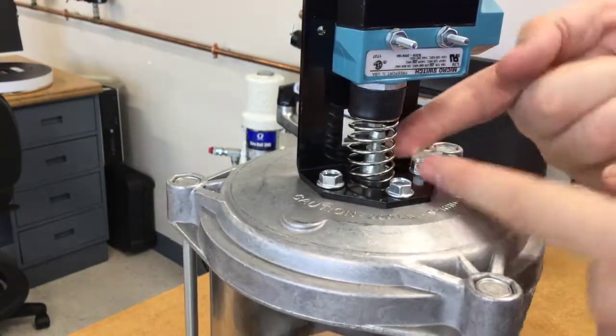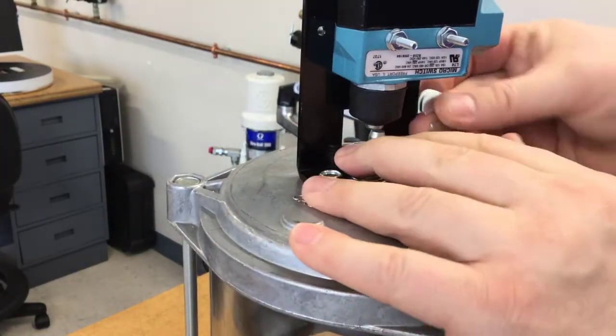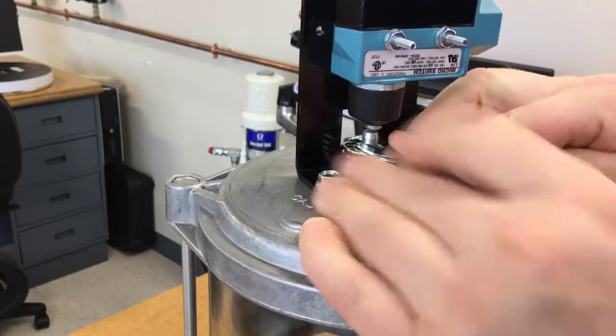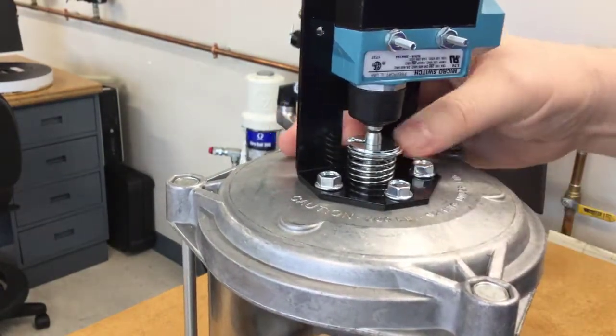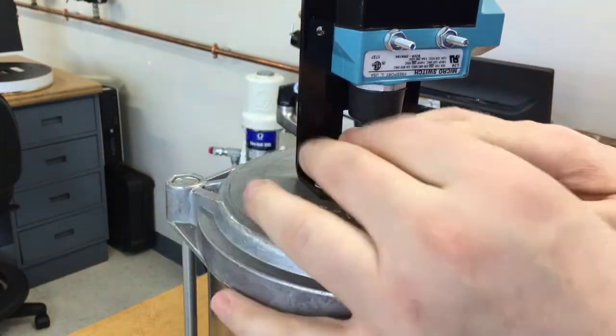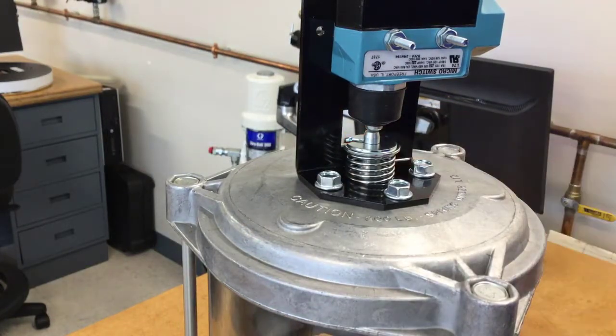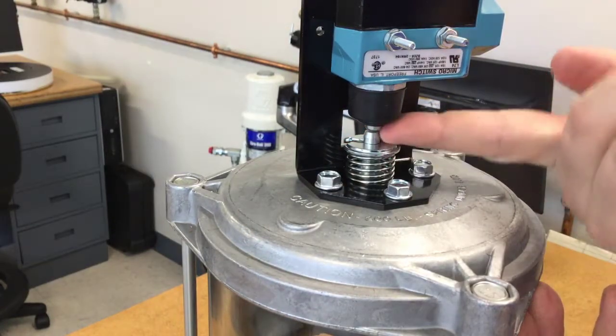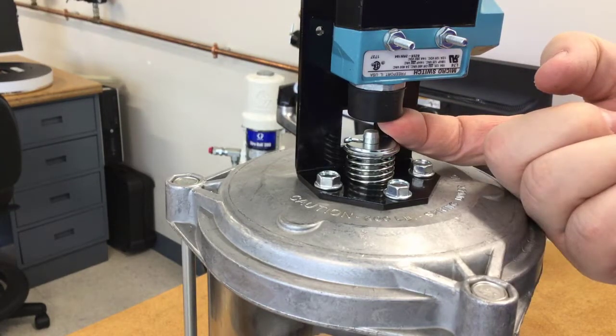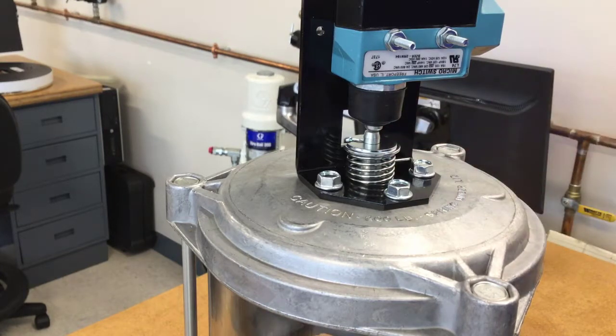Okay, now all three screws have been tightened and we can lift up the switch and squeeze that spring in there. The spring will sit down into the hole inside there to keep it kind of captured, so make sure that it's situated inside this hole in the bracket. Now we can just pull the spring down with our fingers, slide in the retainer, and we're done. Make sure the spring is seated inside the retainer as well. Now whenever the reservoir gets filled, the pin is going to extend up and push that switch in and it will hold that switch in as long as there's grease in it. When it loses grease it's going to descend down and open it up again.